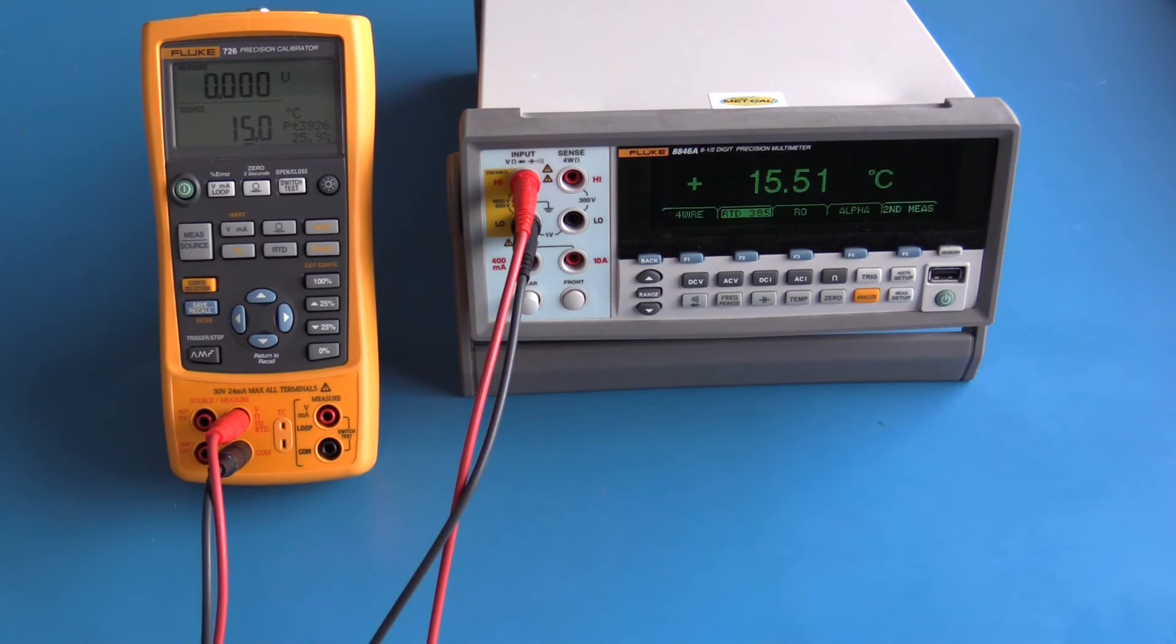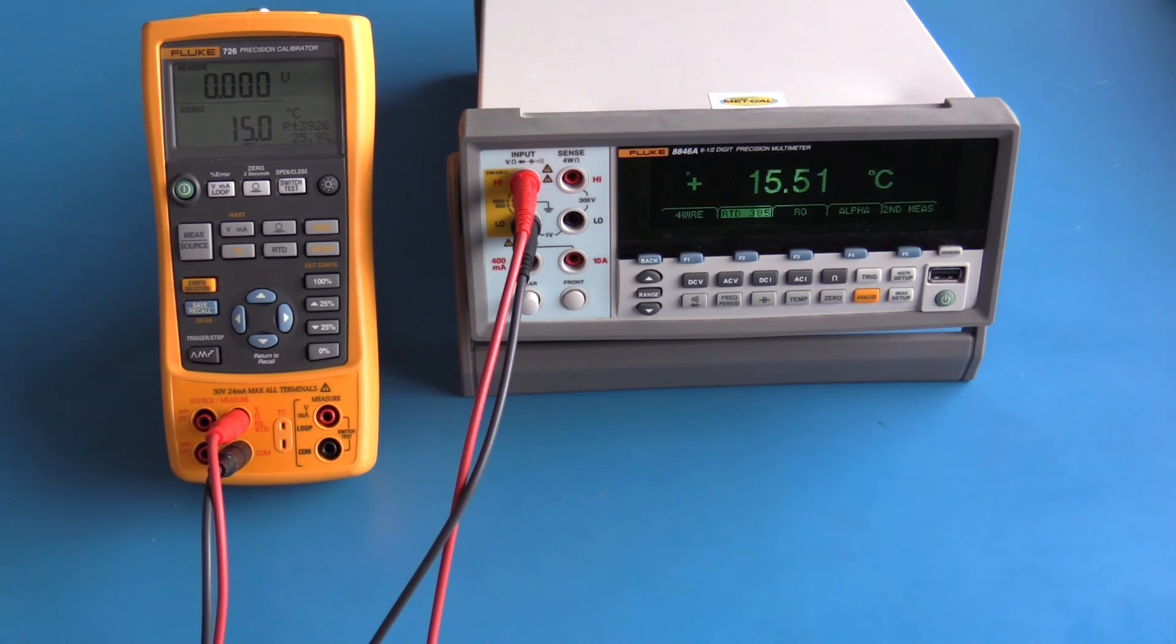The Fluke 726 is also capable of simulating a temperature probe. Here I'm using an RTD and I'm simulating approximately 15 degrees Celsius. There is a slight difference in the type of RTD the Fluke 726 is simulating and the type of RTD the Fluke 8846a is expecting. The Fluke 726 could be set up to simulate the appropriate RTD, I just don't have one set up currently.